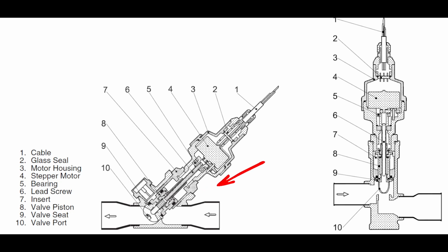You're not going to have very many of these valves that are scaled to this size, if ever, that have a removable stator. And even with this particular style, even if this motor has a failure, you're not going to pull this stator off of the valve body. This whole plunger assembly is one piece.